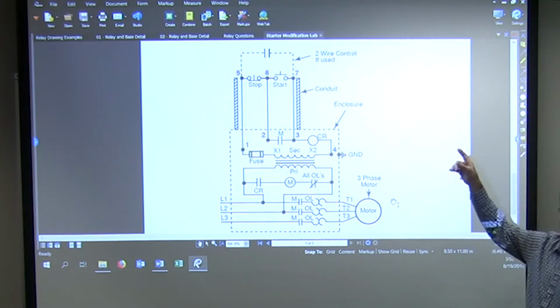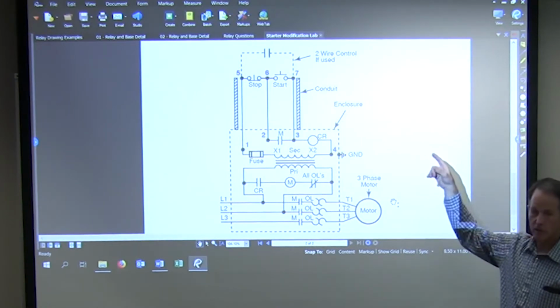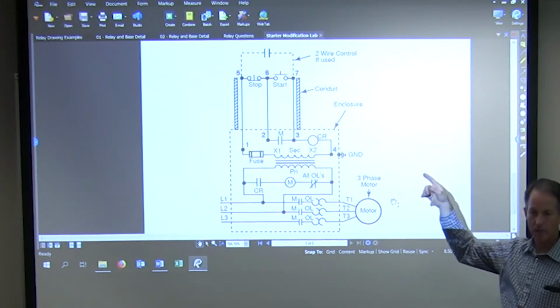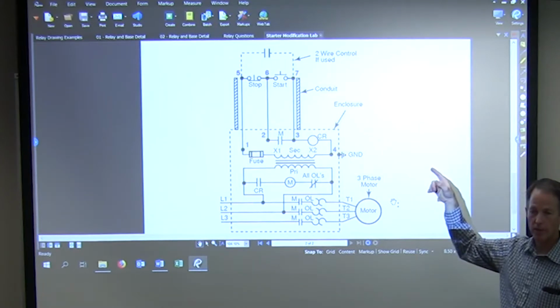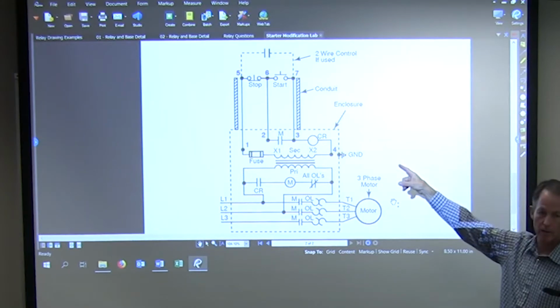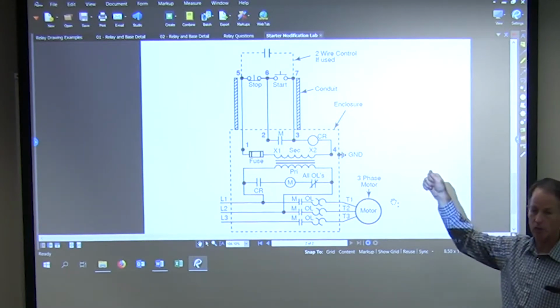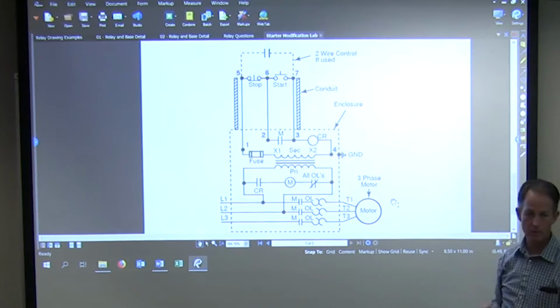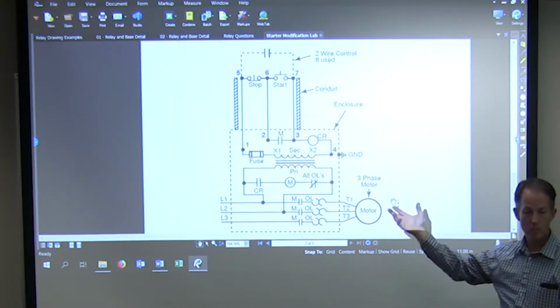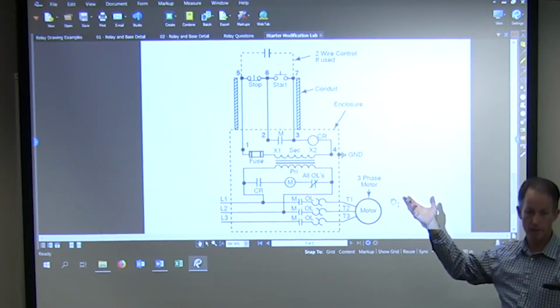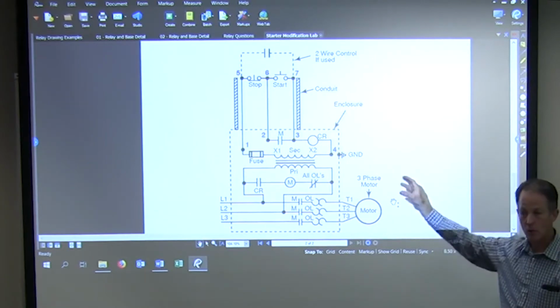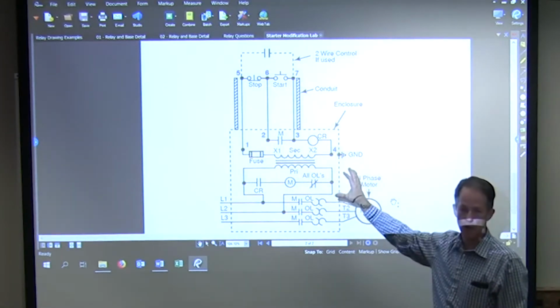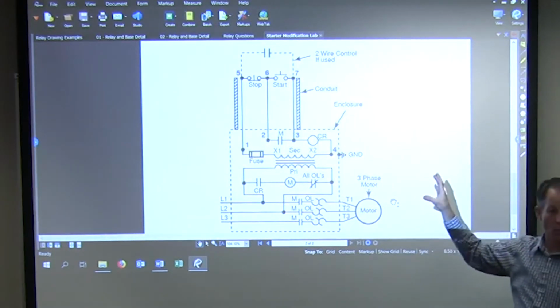If my control system is a held contact, is there any way to stop this, to de-energize it? So if I press the stop button, will it stop if the control signal has that contact closed? It will just run, right? It'll hold it running. Now, if it's momentary, it'll start it, but is there any way to stop it remotely? Not remote. Okay, so the way this is drawn, as is, won't work entirely.